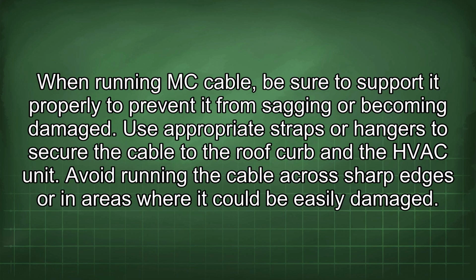When running MC cable, be sure to support it properly to prevent it from sagging or becoming damaged. Use appropriate straps or hangers to secure the cable to the roof curb and the HVAC unit. Avoid running the cable across sharp edges or in areas where it could be easily damaged.